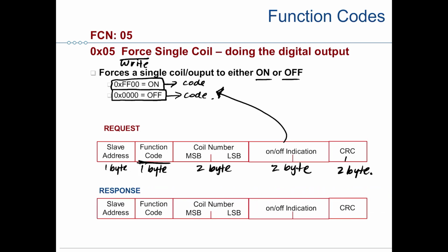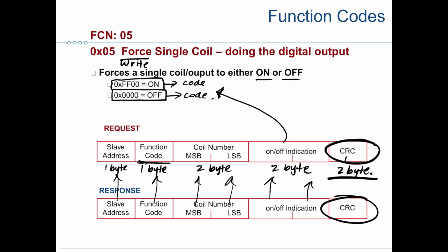And a response then, it's interesting for this one, we have the exact same response coming back as an echo. So it's the exact same values all the way across here, exactly through. Now, that being the case, this is an example of just a couple of the Modbus messages where response and request are going to have the same 2 byte value for CRC.